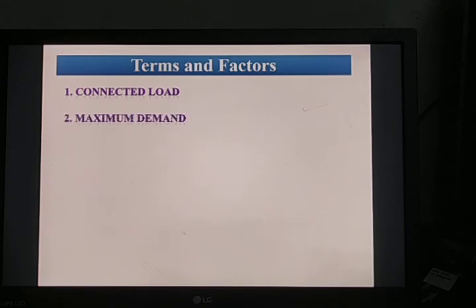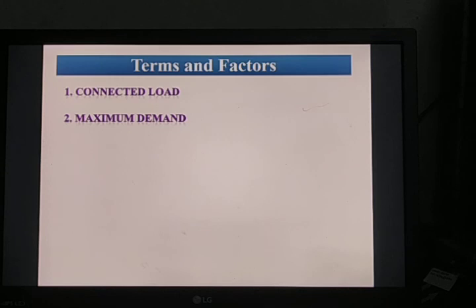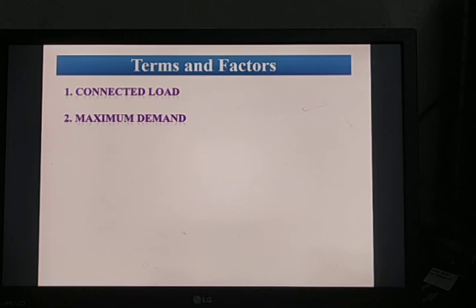The second term is maximum demand, also known as peak demand or load demand. It is the maximum of all loads on a power station during a given period. Maximum demand is always less than or equal to the connected load, because generally not all consumers switch on all their appliances simultaneously. If all consumers switch on at the same time, then the load equals the connected load.